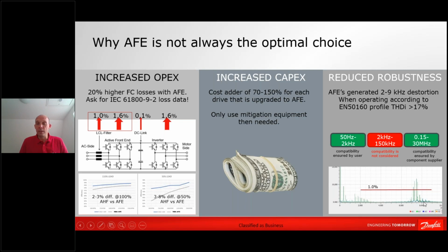And if you really look at this, it will introduce a risk of resonances on your supply. It might resonate with EMC filters and other drives, where you will see overheating, you will see things simply falling out of synchronism or stopping due to resonance issues if you have a lot of AFEs installed. So AFE can be a very good solution, but it needs to be done with caution, I would say.